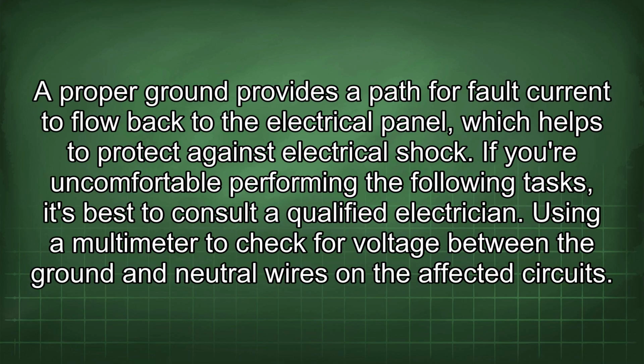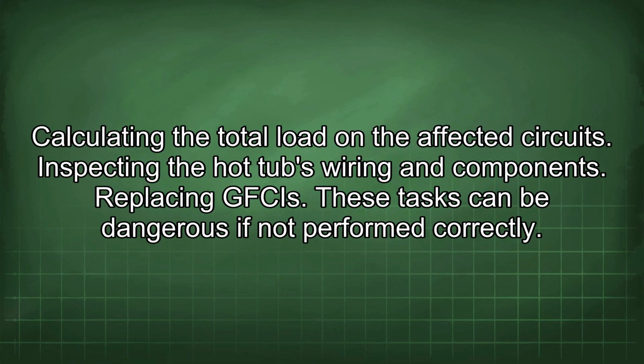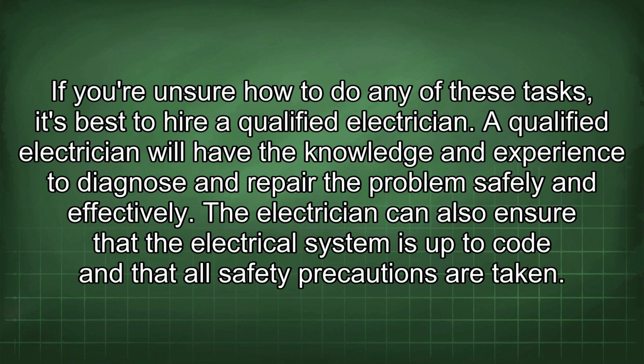A proper ground provides a path for fault current to flow back to the electrical panel, which helps to protect against electrical shock. If you're uncomfortable performing the following tasks, it's best to consult a qualified electrician. Using a multimeter to check for voltage between the ground and neutral wires on the affected circuits. Calculating the total load on the affected circuits. Inspecting the hot tub's wiring and components. Replacing GFCIs. These tasks can be dangerous if not performed correctly. If you're unsure how to do any of these tasks, it's best to hire a qualified electrician. A qualified electrician will have the knowledge and experience to diagnose and repair the problem safely and effectively. The electrician can also ensure that the electrical system is up to code and that all safety precautions are taken.